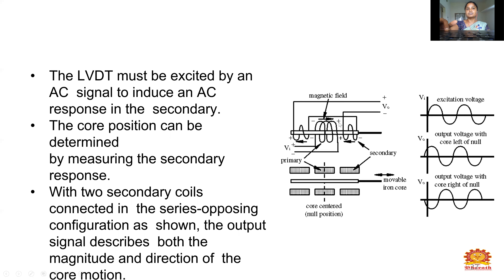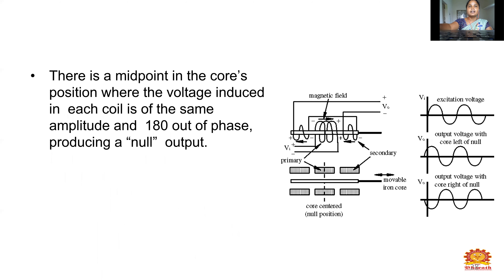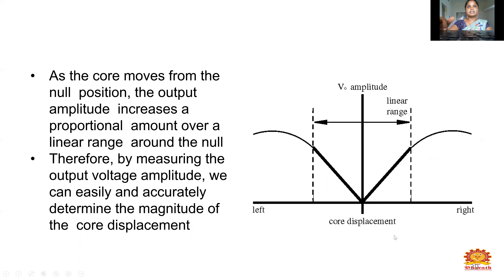Two secondary coils are connected in a series opposing configuration. The output signal describes both the magnitude and direction of the core motion. At the midpoint — the null position — the voltage induced in each coil is of the same amplitude and 180 degrees out of phase, producing a null output. As the core moves from the null position, the output amplitude increases proportionally over a linear range around the null. Therefore, by measuring the output voltage amplitude, we can easily and accurately determine the magnitude of the core displacement.